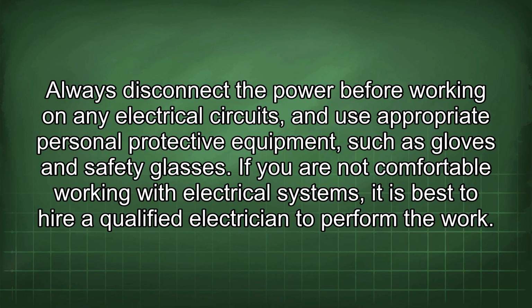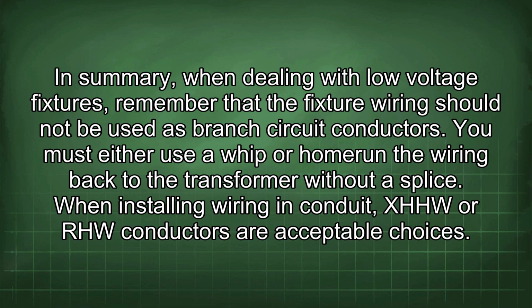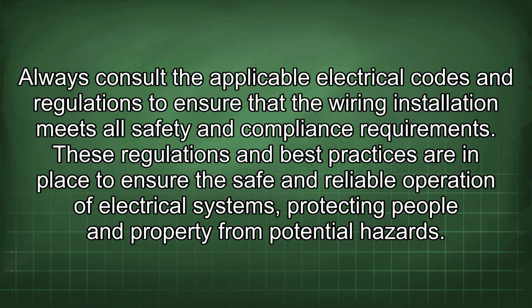perform the work. In summary, when dealing with low-voltage fixtures, remember that the fixture wiring should not be used as branch circuit conductors. You must either use a whip or a home run the wiring back to the transformer without a splice. When installing wiring in conduit, XHHW or RHW conductors are acceptable choices. Always consult the applicable electrical codes and regulations to ensure that the wiring installation meets all safety and compliance requirements.